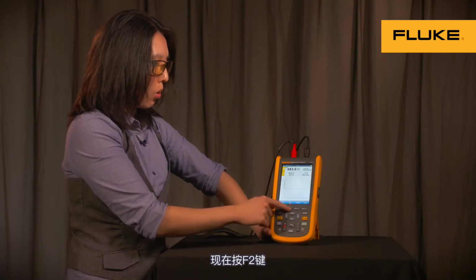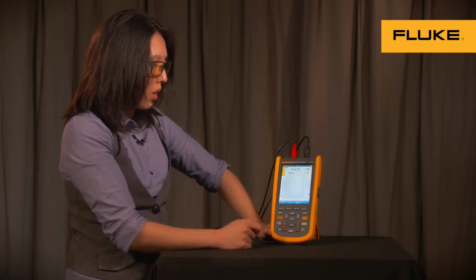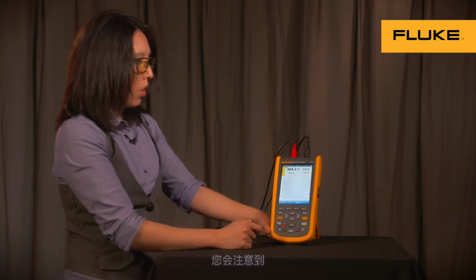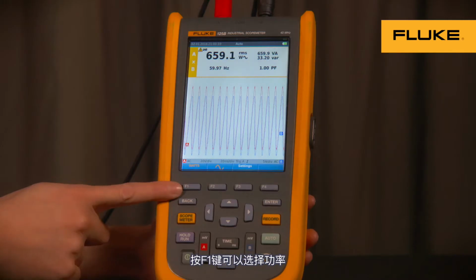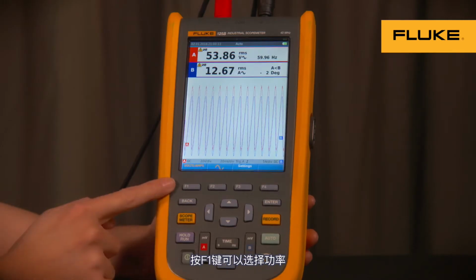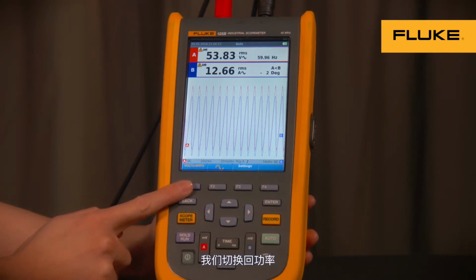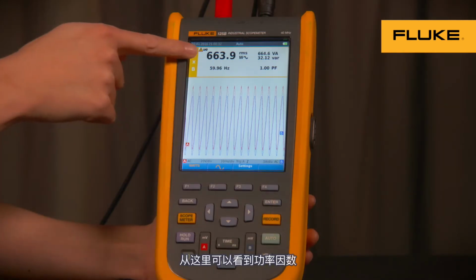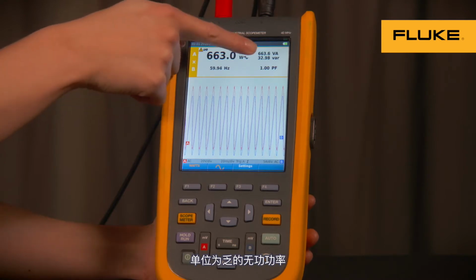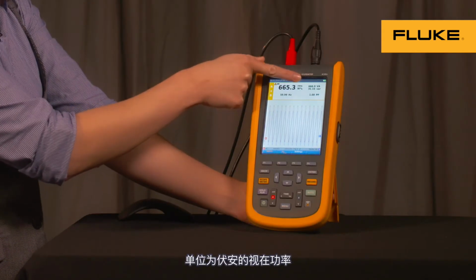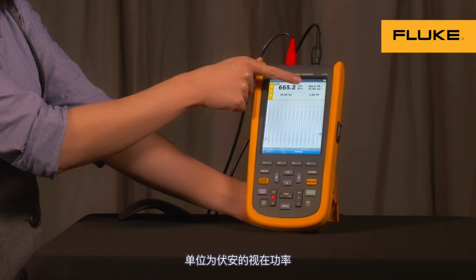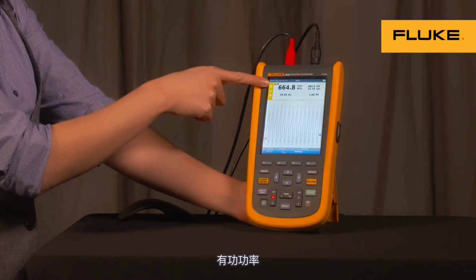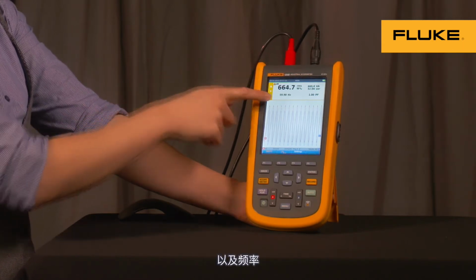Now let's toggle, by pressing F2, to the waveform. You notice here, you may choose watts by toggling F1, or volts amps by pressing F1. So let's toggle back to watts. Here you can see your power factor, your reactive power in VARs, volt amps reactive, your apparent power, which is in volt amps, and your real power, watts, as well as frequency.